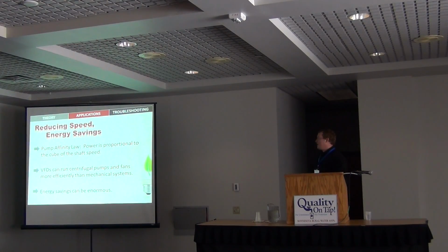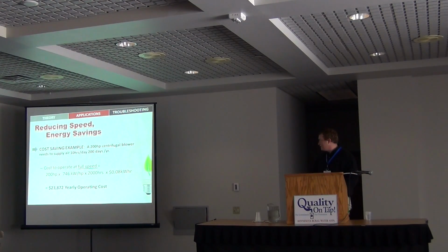Number one, the pump affinity law. Power is proportional to the cube of the shaft speed. What that means is if we slow this motor down, we're going to save a lot of money and energy. So we can use these VFDs to run centrifugal fans and blowers, pumps, and mechanical systems more efficiently. A lot of times a mechanical system that's run across the line has some sort of pulley system to reduce the speed of the fan. We can do that with a VFD and eliminate that system. And this can add up to a lot of money. And we all like money.